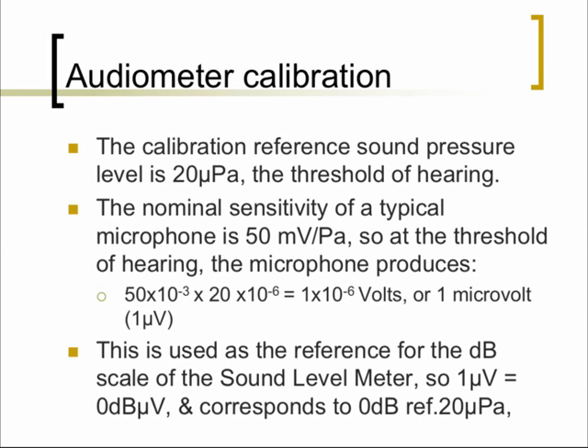The present standard is 20 micropascals, considered the threshold of hearing. That's based on a sample of the average normal hearing person. If something dramatically changes over a decade, one would have to change this reference value depending upon what's considered the nominal hearing threshold at that period. In reference journals and specifications of acoustical or audiological equipment, the sound level meter standard is 1 microvolt for 0 dB, equivalent to 0 dB SPL referenced to 20 micropascals.